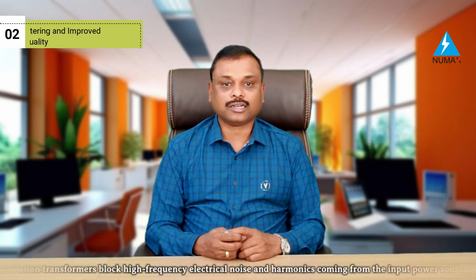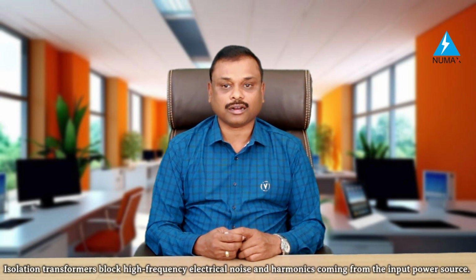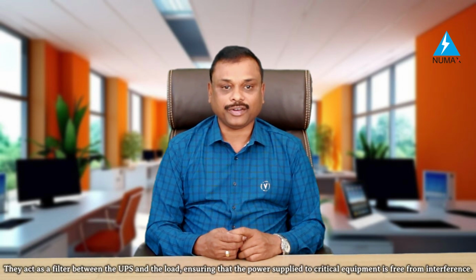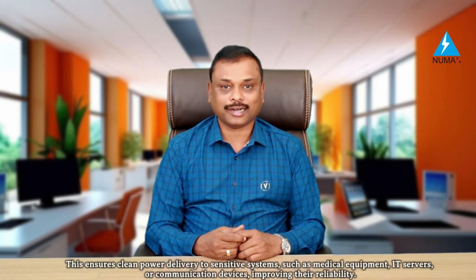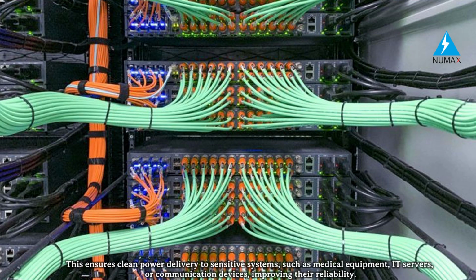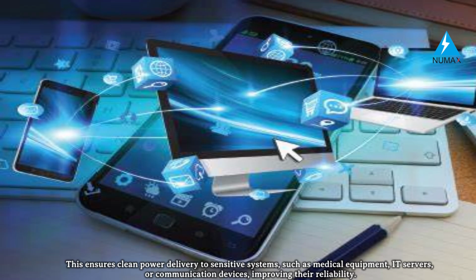Number 2. Noise filtering and improved power quality. Isolation transformers block high frequency electrical noise and harmonics coming from the input power source. They act as a filter between the UPS and the load, ensuring that power supplied to critical equipment is free from interference. Benefits: this ensures clean power delivery to sensitive systems such as medical equipment, IT servers or communication devices, improving their reliability. Number 3. Eliminates ground loops.